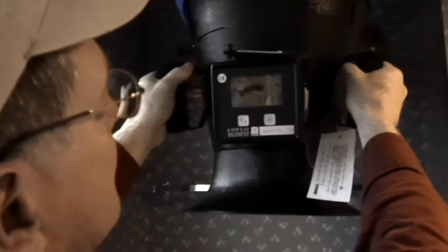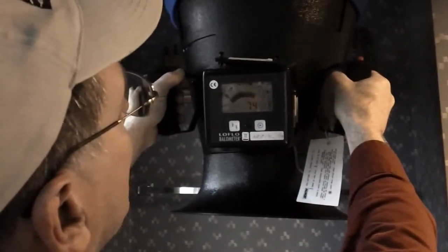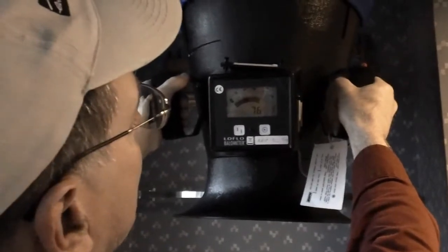And here we're testing a new fan that was installed as part of the energy retrofit on this house. It's an Energy Star rated fan. It's very quiet, efficient, and it has quite a bit of air volume compared to the other two fans, which are original to the house or quite old. And we're measuring 75 cubic feet of air, 76 cubic feet of air. This is very good ventilation for a bathroom this size. This bathroom is probably used the most, so it's important to get moisture out of it.